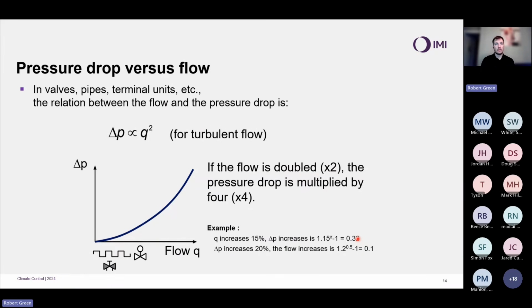Conversely, if we said, okay, I can only increase by 20% on my pump head, a 20% increase in differential pressure leads to a flow increase of 120% to the power of 0.5, or the square root of 120%, i.e. a 10% increase in flow. So due to the inverse square law, a 20% increase in differential pressure only leads to a 10% increase in flow.